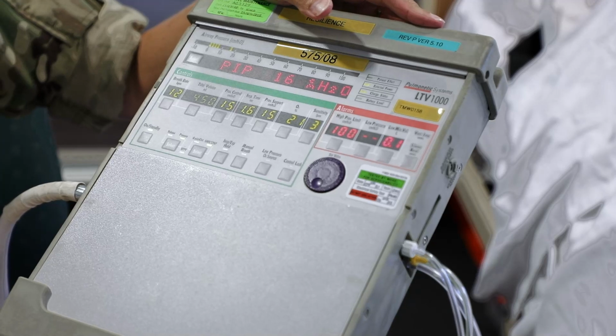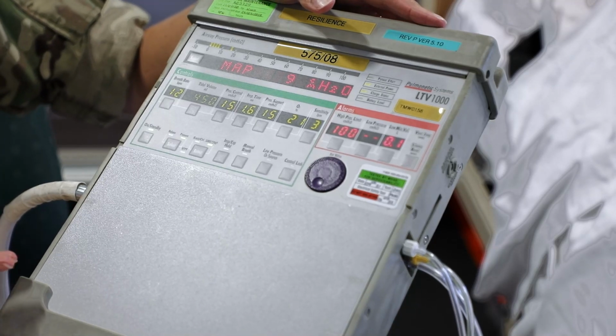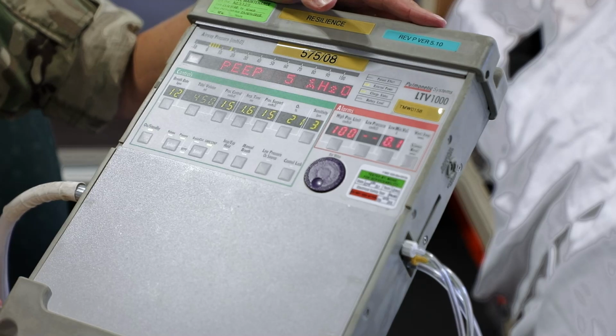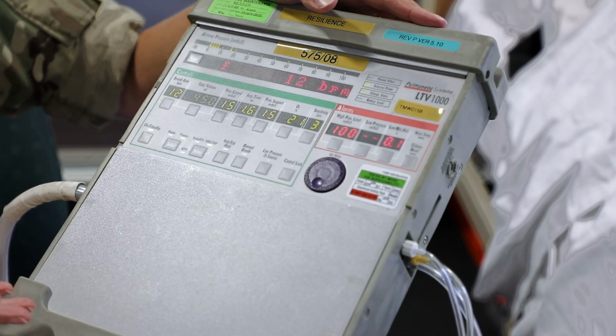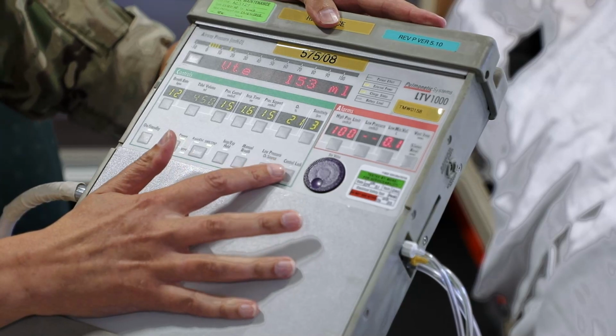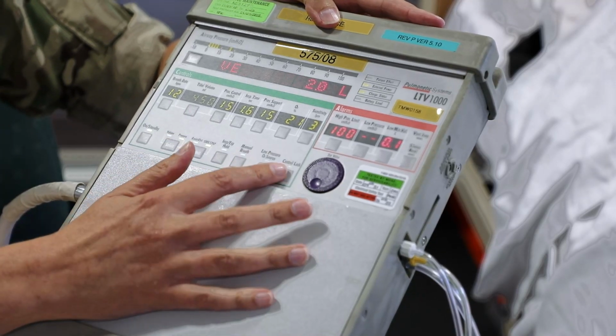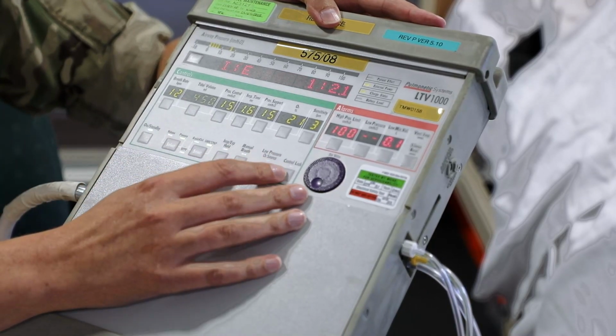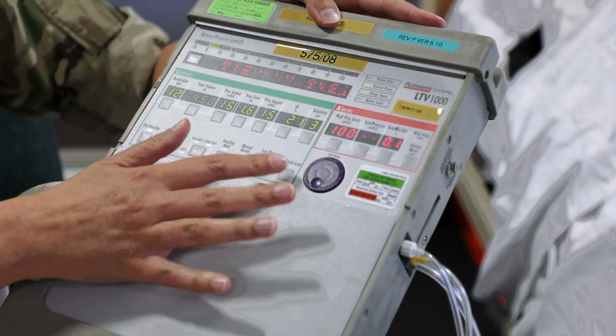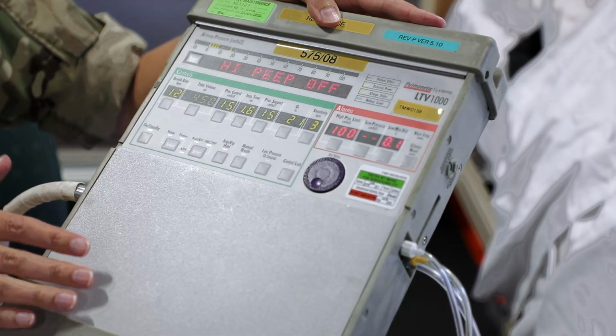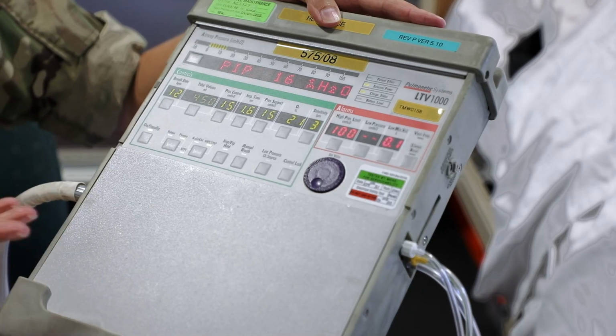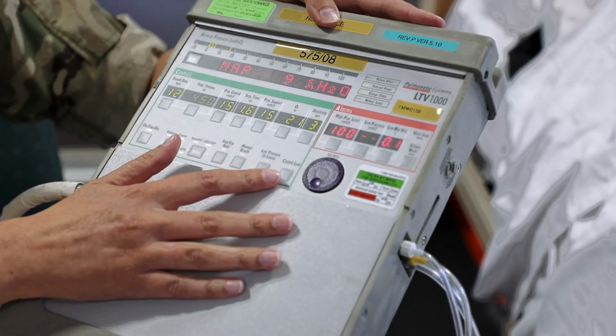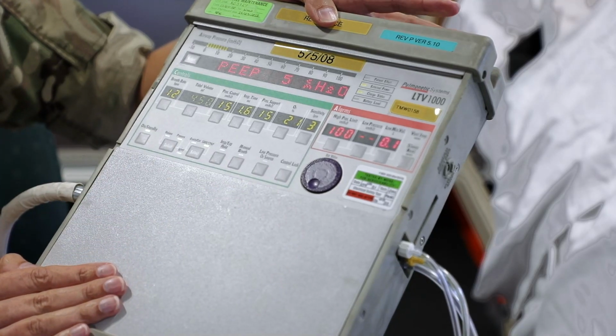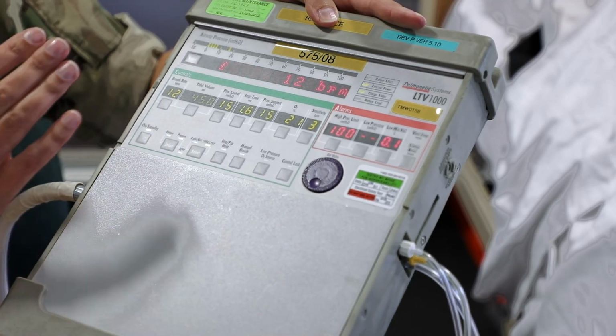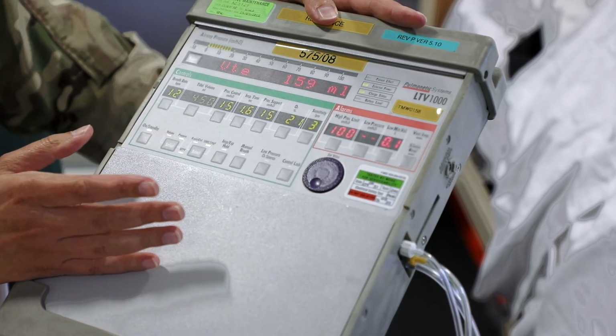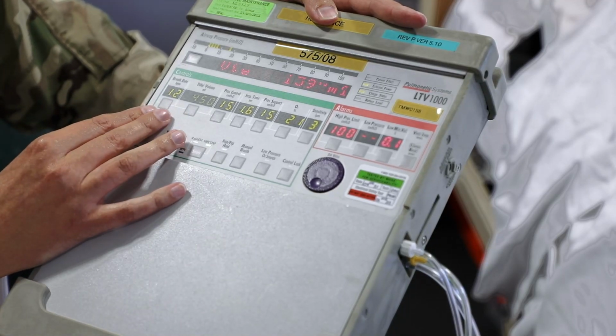So moving on to real-time transducer data, you'll see here that the ventilator is obviously ventilating. How I got out of that last menu was by pressing this control lock button. If you press it, it acts like a back button. Press it once and it took me into the upper menu, pressed it again and it took me out of menus and into a ventilation mode. Alternatively, you can switch the whole ventilator off and on again, but that is just the quickest way to get into a ventilation mode. From here, the checklist talks about doing this real-time transducer data in a set mode.